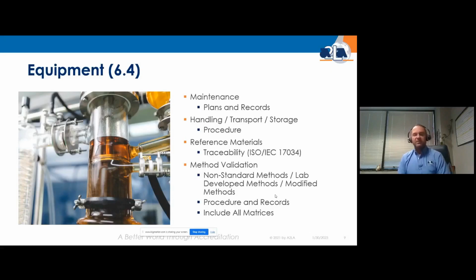And when we're talking reference materials, this is what you would use to calibrate your HPLC, your ICP, or your GCs when you're setting up your calibration curve. And these reference materials also need to be traceable. And that traceability can be demonstrated by purchasing your reference materials from a 17034 accredited reference material provider.